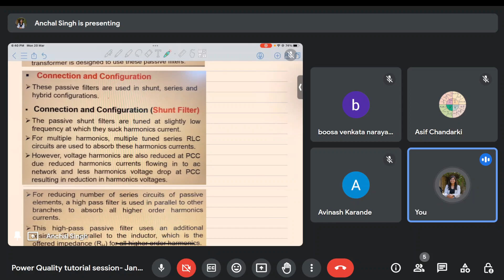So now we talk about the connection. Based on the connection, we have shunt, series, and hybrid configurations, right? If we talk about the shunt filter, first of all, the shunt filters are tuned at a slightly low frequency relative to the one at which they want the harmonics to be compensated. Suppose I want to take care of a fifth order harmonic. Then instead of designing my system directly for fifth order harmonic, what we actually do in practical conditions is we design for 4.7th harmonic or any other harmonic which is less than 5.